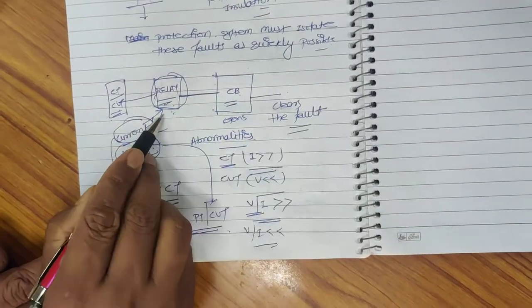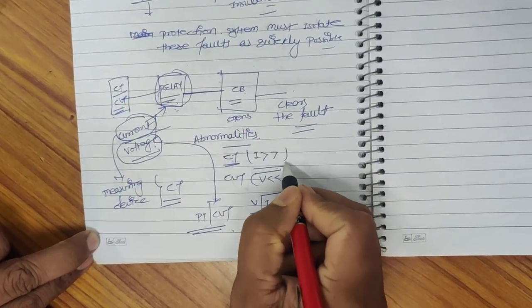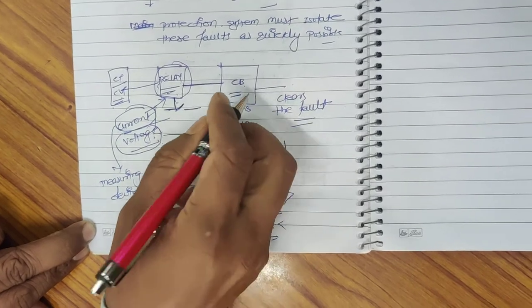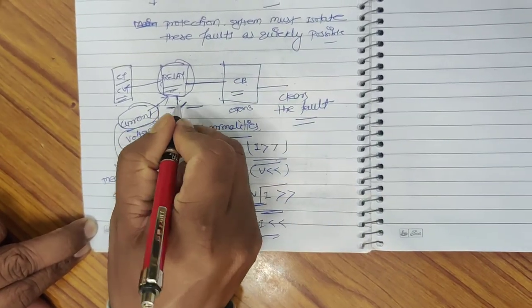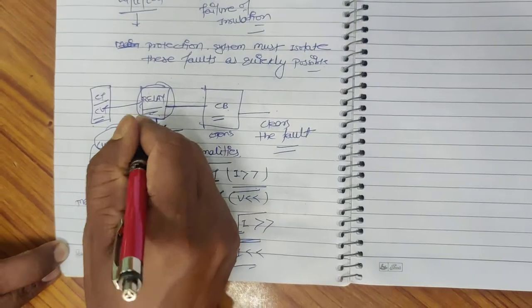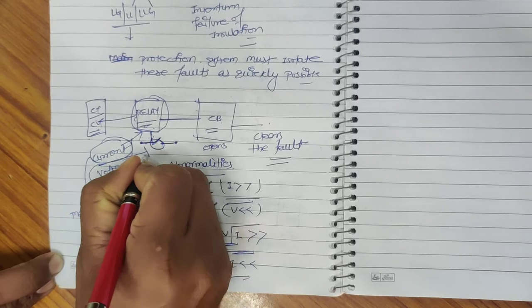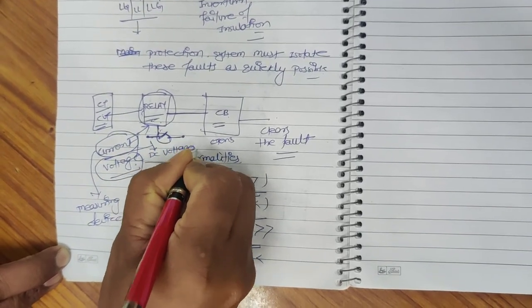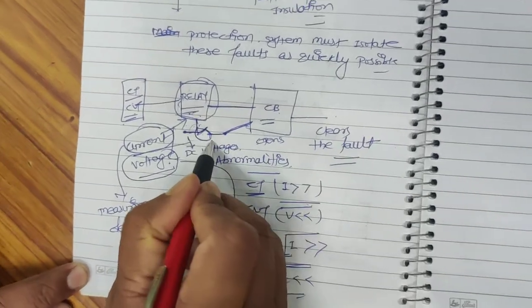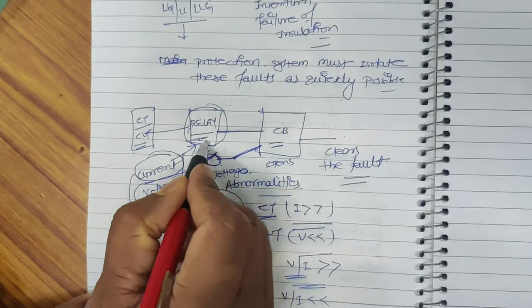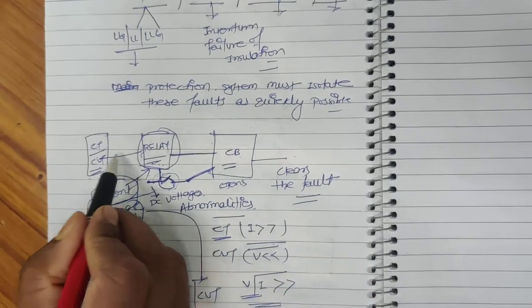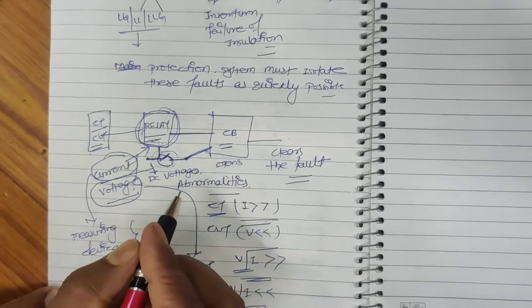After detecting a fault based on its algorithm, the relay has one output contact. This output contact is used to trigger the circuit breaker for clearing the fault. This output contact is basically a simple mechanical or electrical contact, wired from a DC voltage source and connected to the circuit breaker. Now, if this contact does not operate — even if the relay detects the fault correctly — the fault will not be cleared. Similarly, if the relay itself fails to operate, the fault will not be cleared. So there are chances that failure of even a single element will lead to non-clearance of the fault.